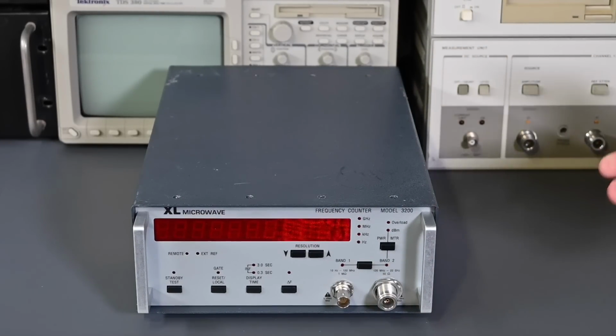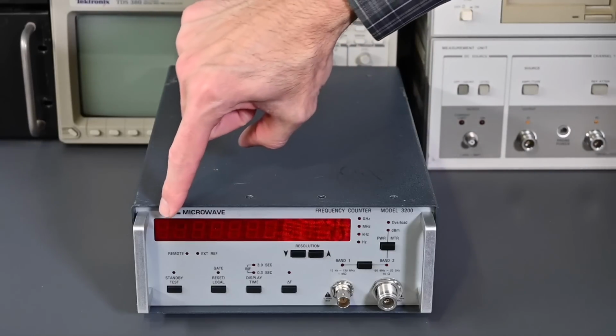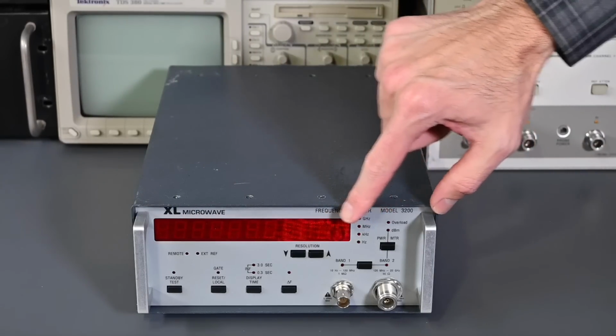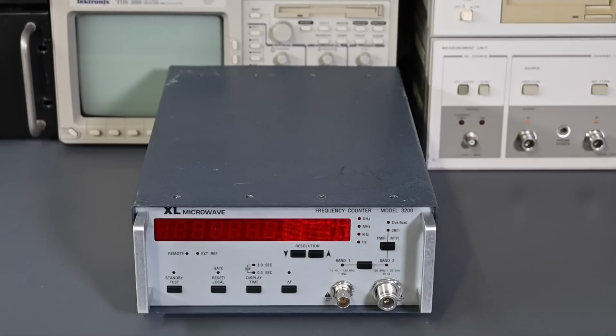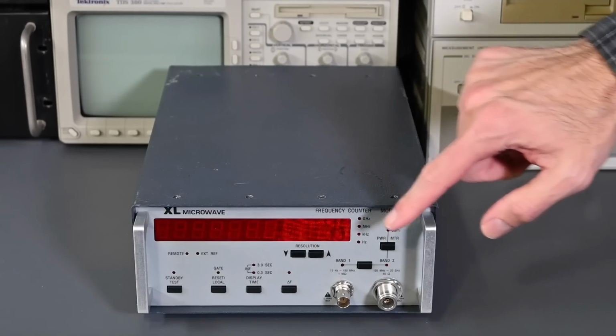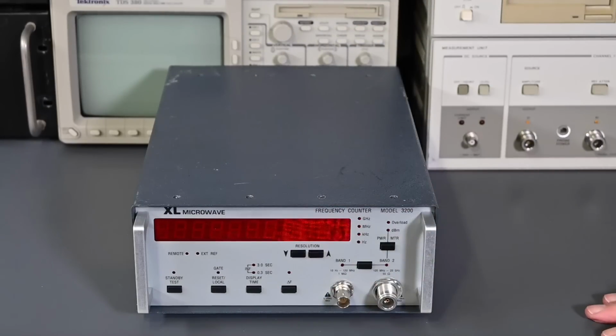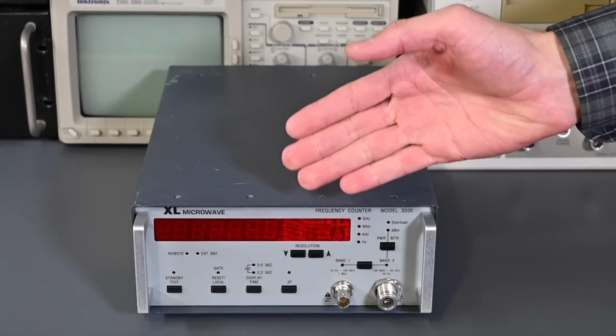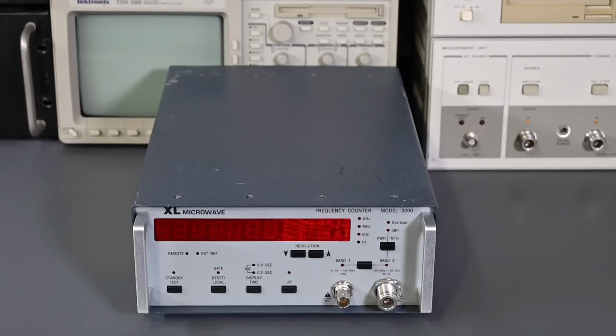And also, I don't know if this can be seen on the camera, but this window for the LED display has a very, very fine mesh that's embedded inside that window, and it acts like an RF shield. So if you didn't have that mesh in there, this would just act like a big opening in the front panel, and you could have interference passing in and out. So the mesh is very fine, and it doesn't interfere with the viewing of the LED display, but again, it acts like an RF shield.